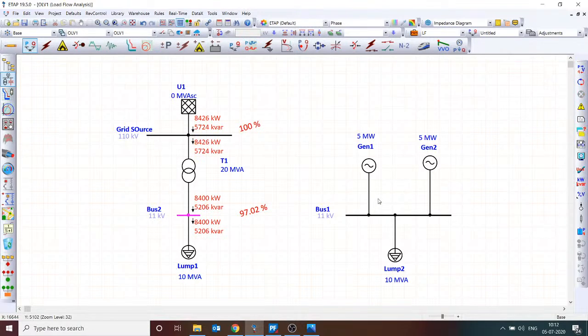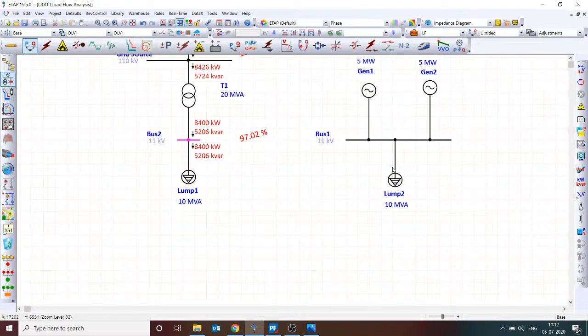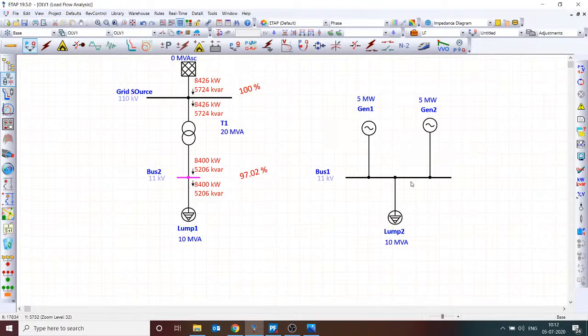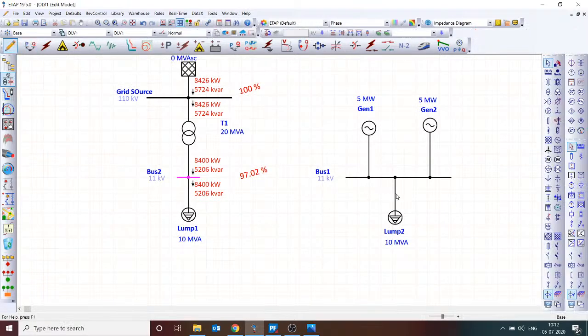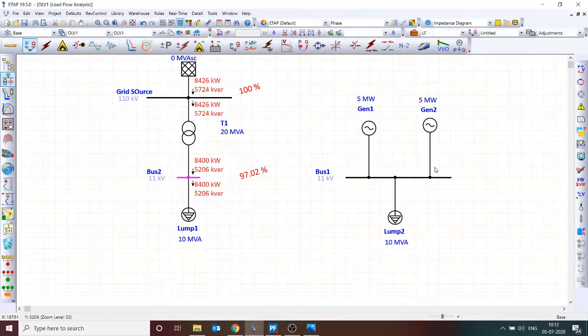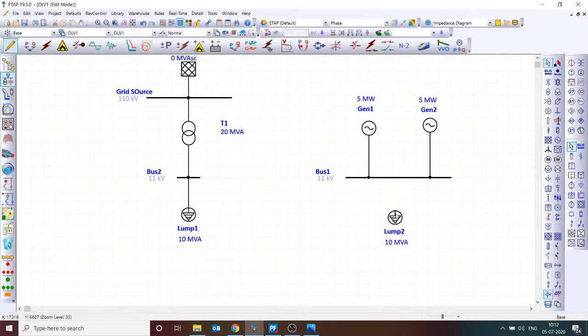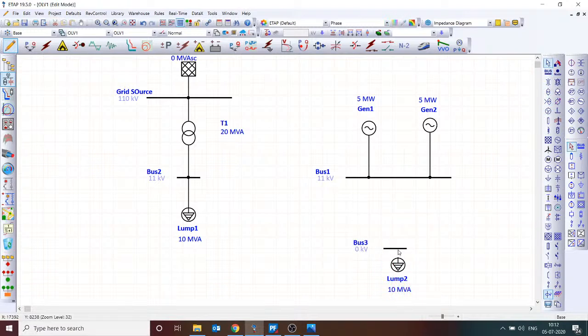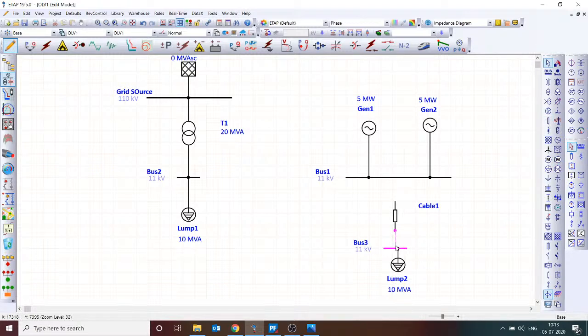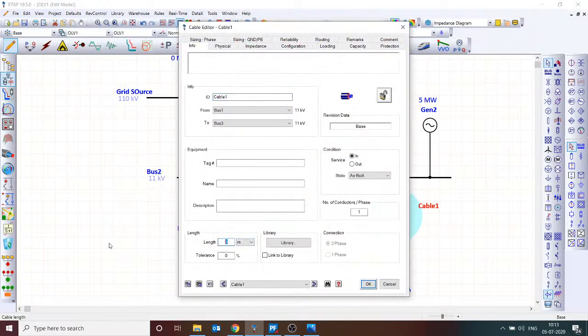The load flow doesn't run here. The simple reason is that in ETAP, to run a load flow you need at least two buses. With only one bus, the load flow will not solve in ETAP. Some other simulation software supports a single-bus system. So let me add a small cable to create a second bus, just to enable the load flow analysis — even though this is only for illustrative purposes.